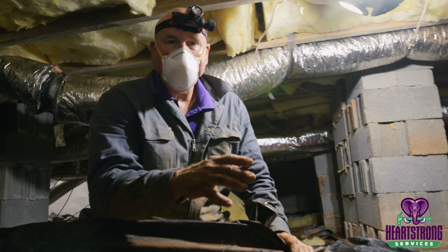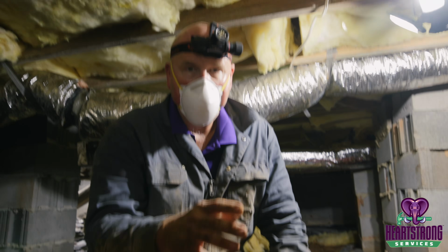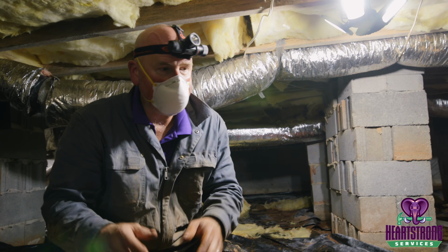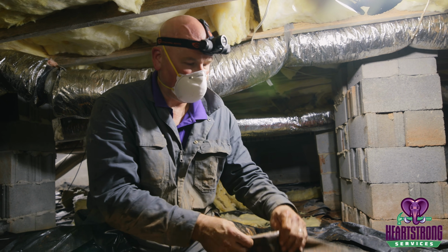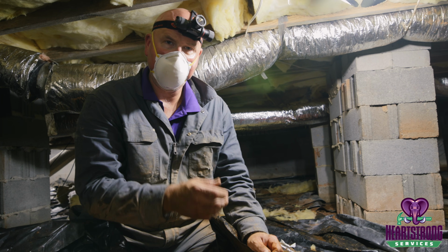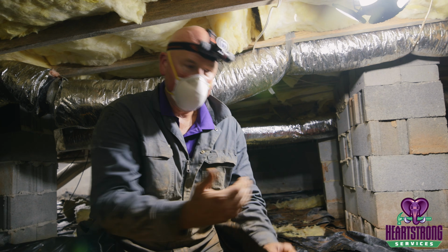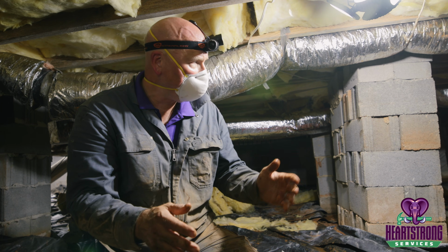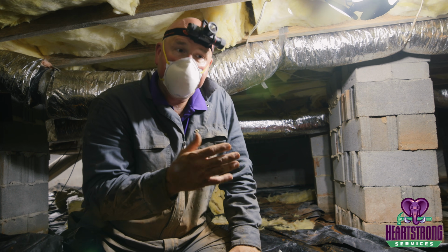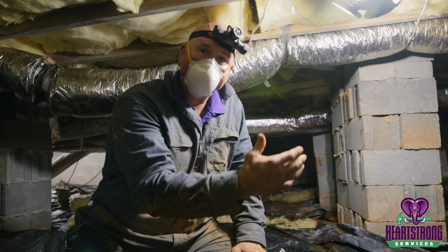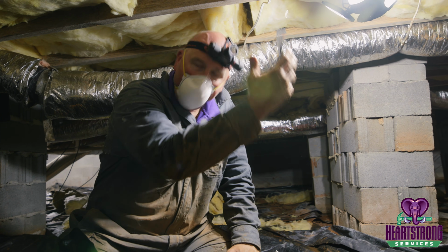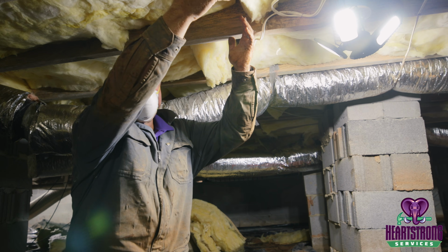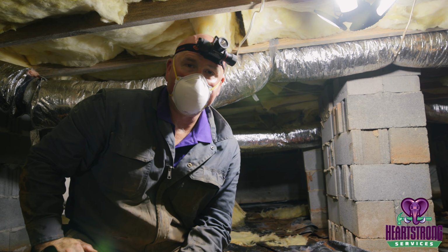So one of the things we're looking at is not just, is there a vapor barrier? Is it in good working condition? We also pay attention to what its thickness is because we want to pay attention to things like what's its permeability rating, how much moisture and soil gas goes through that particular liner. And then most importantly, are there any gaps in the liner? Is it missing in areas? Is there exposed soil? Because that again is going to allow that water vapor to come up and go where? It's going to come up and get inside of the wood and eventually contribute even to the moisture inside the home.